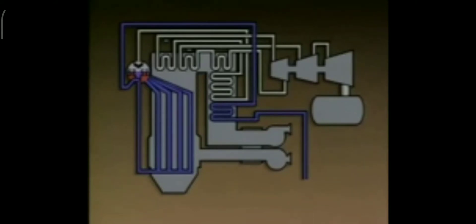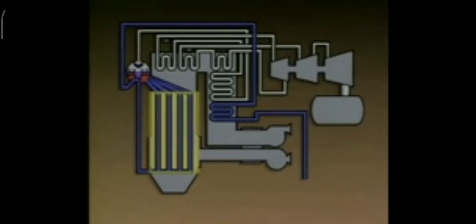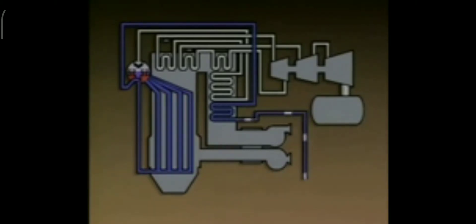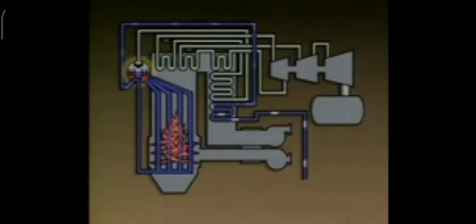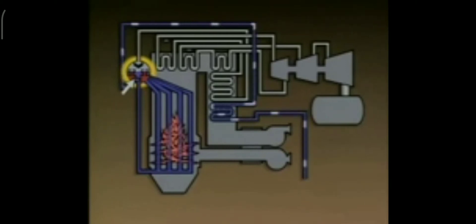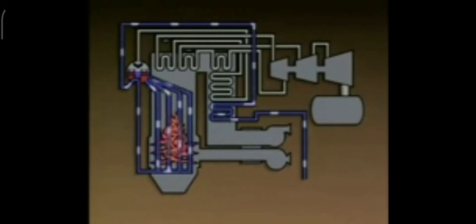The water flow path includes an economizer, the boiler drum, downcomers, headers, and the boiler tubes. The water supplied to a boiler is called feed water. The first component that the feed water passes through is the economizer. The economizer uses heat from combustion gases that would otherwise flow out of the stack to heat the feed water. Heating the feed water means that less fuel has to be burned in the furnace to convert the water into steam. In this boiler, the heated feed water flows from the economizer and enters the bottom part of the boiler drum through the feed water inlet. The water continually circulates within the boiler through the downcomers, the lower headers, and the boiler tubes.